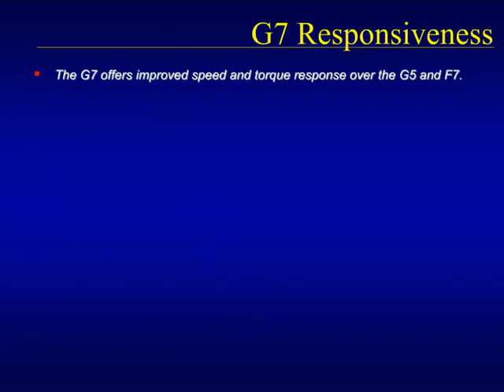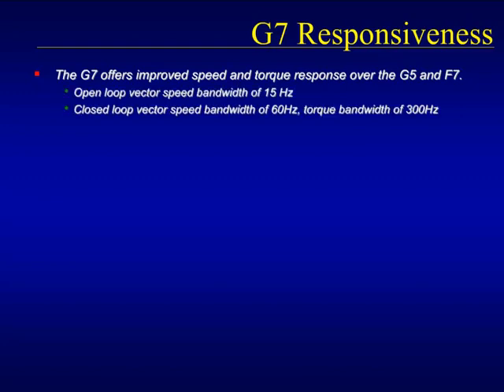The speed response bandwidth of a drive refers to the drive's quickness in tracking rapid changes in the frequency reference or instantaneous changes in the load, also known as shock loading. The speed response of the G7 in both the open-loop vector and closed-loop vector modes has improved over what was available previously from the G5 drive and the F7 drive.